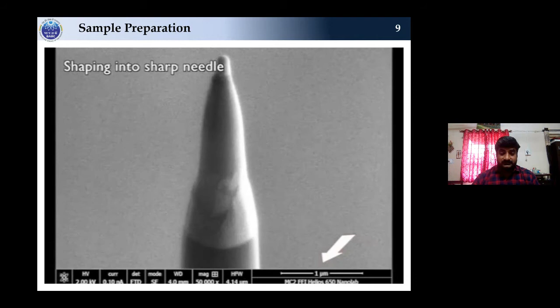In the case of atom probe, the significance of the sample is very high. Why am I saying this? Because the specimen itself is optics in atom probe tomography. For example, in a transmission electron microscope or TEM, once you prepare the sample, to get a better image one has to do adjustments on different optics. Like you adjust the condenser lenses, you make changes on the objective lenses, you change the aperture, so that you can get a good image on the phosphor screen. But in atom probe tomography, the specimen itself is optics.